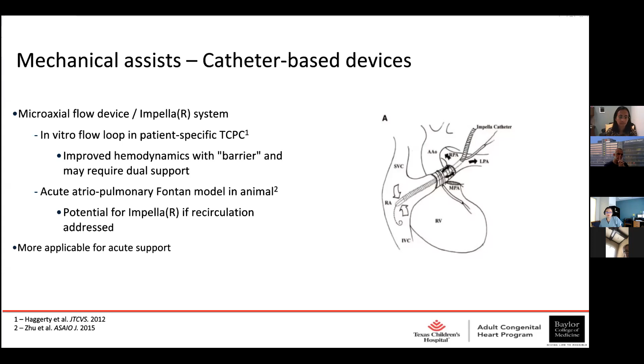This is an interesting device using rotating discs to draw fluid in from the Y direction, from the SVC and the IVC, and then radially accelerate the fluid in the x-axis to the LPA and RPA. There have been some computational studies and flow loop studies showing that when the device is stopped, with no power to it, it doesn't move. There's actually a reduction or no power loss when it's stationary. So if it were to have a problem, it wouldn't cause circuit obstruction.